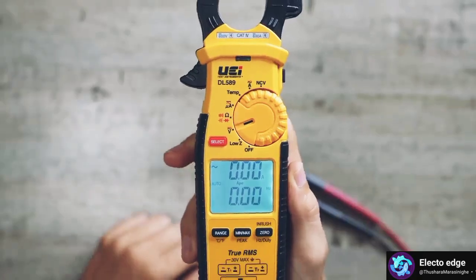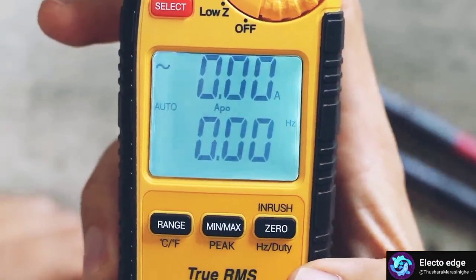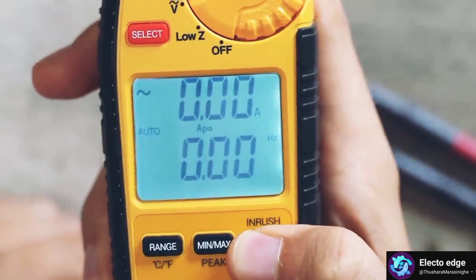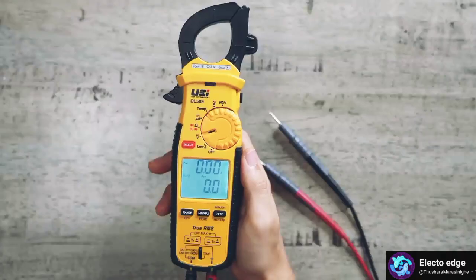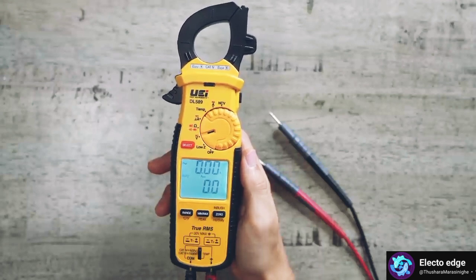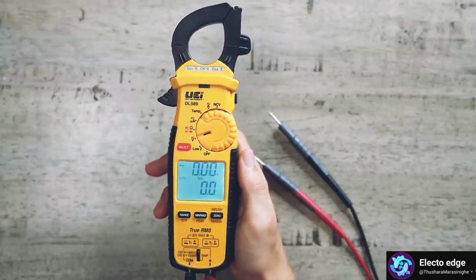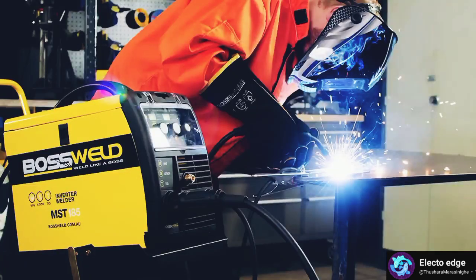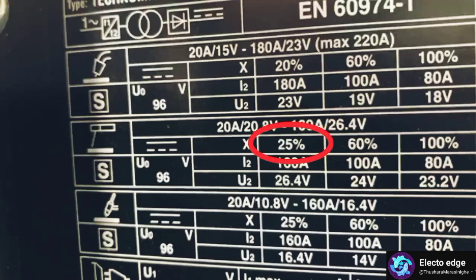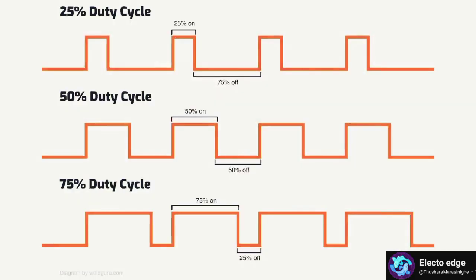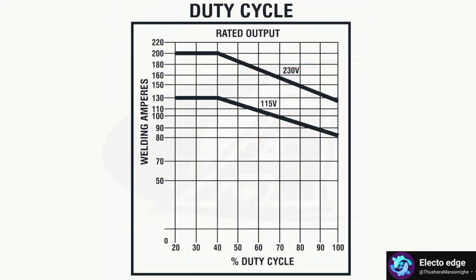And the last cycle I'm going to go over is the duty cycle, which is usually labeled as duty or a percent symbol. The duty cycle is used to determine the ratio of time a load or a circuit is on compared to the time that it is off. For example, if you have a welding machine that has a duty cycle of 25%, that means that machine can run at a designated amperage for 2.5 minutes, followed by 7.5 minutes of cooldown. Which means if you need to be welding continuously for a long time, 25% duty cycle is actually bad. You'd probably want something that is at least 50 or more.